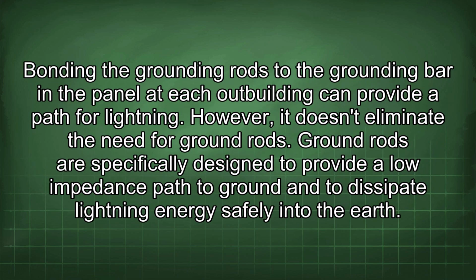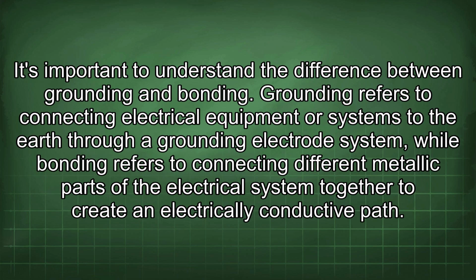hazards. Bonding the grounding rods to the grounding bar in the panel at each outbuilding can provide a path for lightning. However, it doesn't eliminate the need for ground rods. Ground rods are specifically designed to provide a low impedance path to ground and to dissipate lightning energy safely into the earth. It's important to understand the difference between grounding and bonding. Grounding refers to connecting electrical equipment or systems to the earth through a grounding electrode system, while bonding refers to connecting different metallic parts of the electrical system together to create an electrically conductive path.